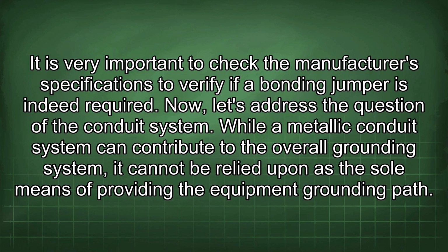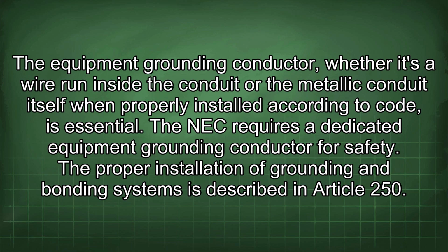Now let's address the question of the conduit system. While a metallic conduit system can contribute to the overall grounding system, it cannot be relied upon as the sole means of providing the equipment grounding path. The equipment grounding conductor, whether it's a wire run inside the conduit or the metallic conduit itself when properly installed according to code, is essential. The NEC requires a dedicated equipment grounding conductor for safety.